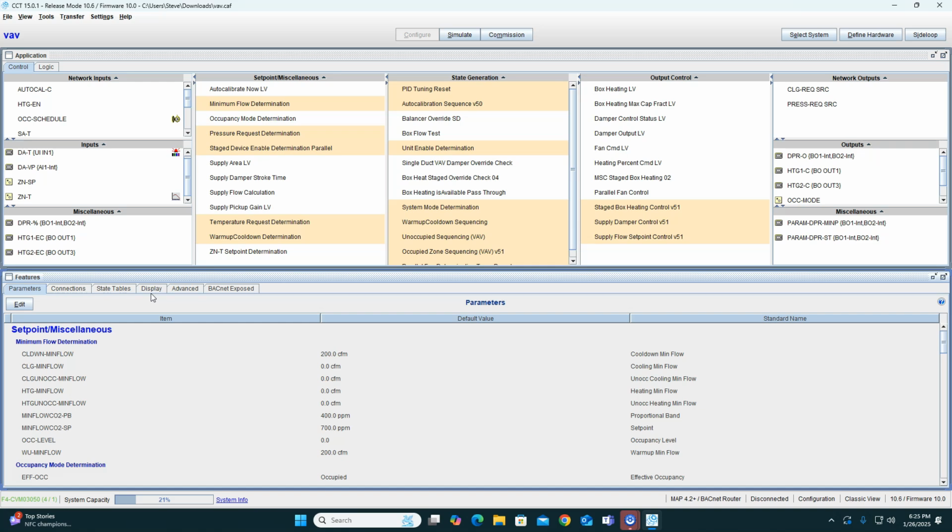So it'll tell me what controller that is, so I can mark it on my little notebook, a general location of where it's at, and I can map out a whole building in a few hours instead of popping open the ceiling tile, taking a picture of the address of the controller or whatever you got to do. You know, pop open the ceiling tile, take the cover off the controller or the VAV or fan power box, open up the door and write down the address of the controller. That takes time instead of just going and plugging in, marking it down, go to the next one, plug in, mark it down.